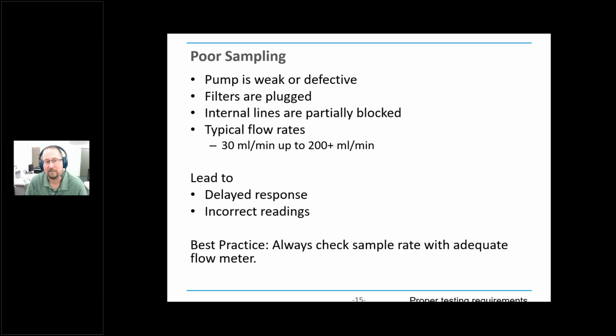And so the best practice for looking for failures in the sampling area is to always check the sample rate. And you need to make sure you're using an adequate flow meter. As part of this funding from NIH, we went into dozens of biomedical shops and interviewed them and watched them and looked at how people were doing testing, again looking for best practices. One thing we noticed is a lot of people are using a flow meter that's not adequate to check these low flow rates. If you're using a flow meter that's used for vent testing, it's not accurate enough to test down in this 30 milliliter a minute range. You really need a flow meter that's designed for these lower flows. We see that missing in a lot of shops.